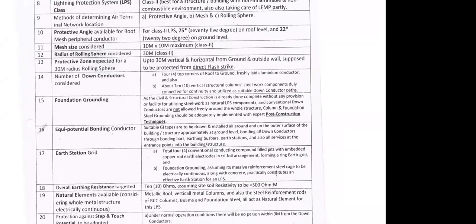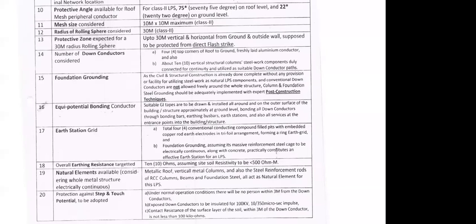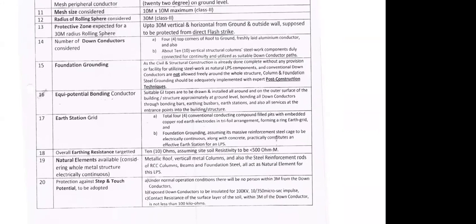This is basically GI tapes, to be drawn and installed all round and on the outer surface of the building. Earth station grid: it depends on the lightning, but I discussed 150 kiloampere or 100 kiloampere, whichever you are talking about. Now the number of down conductors has to be designed based on that. Here we have considered a total of 4 conventional conductors, but it is not sacrosanct. It may change based on the design, and the overall earthing resistance targeted is 10 ohms.